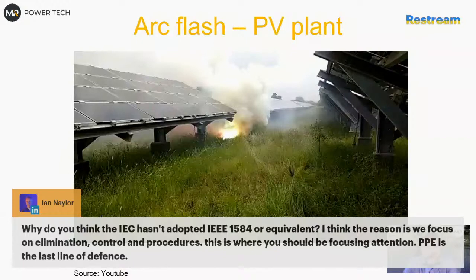What I'm a bit afraid of is that most likely the IEC, like everyone else, will try to make their own way of doing a lot of things instead of adopting IEEE 1584. I would prefer IEEE 1584 to be generally adopted because it's an international standard. I'm just adapting this to the IEC world when I do calculations - I don't follow NEC, I follow IEC because everything else fits, and it has to be in line with the protection rating and everything else, and it's relatively easy to do.